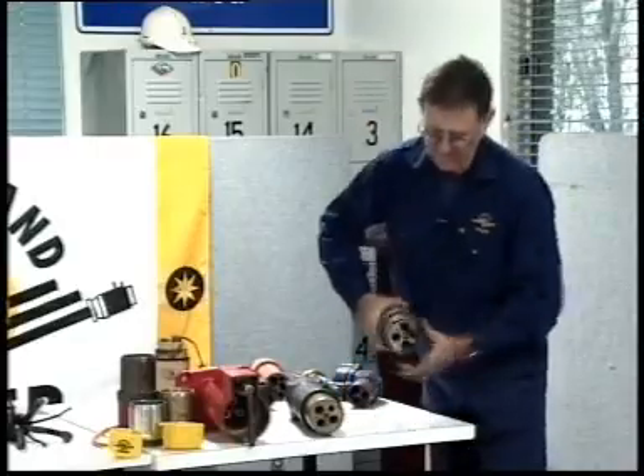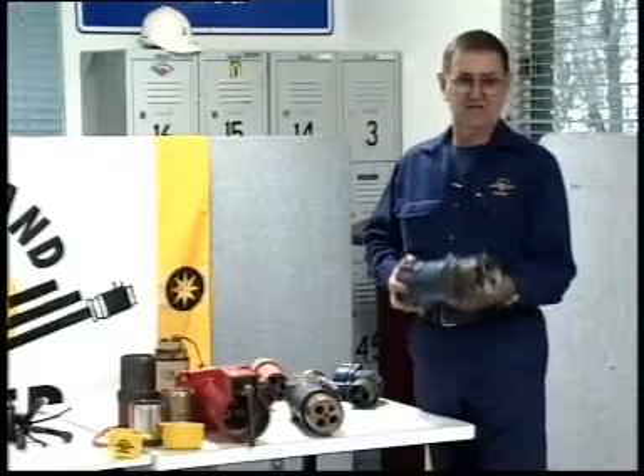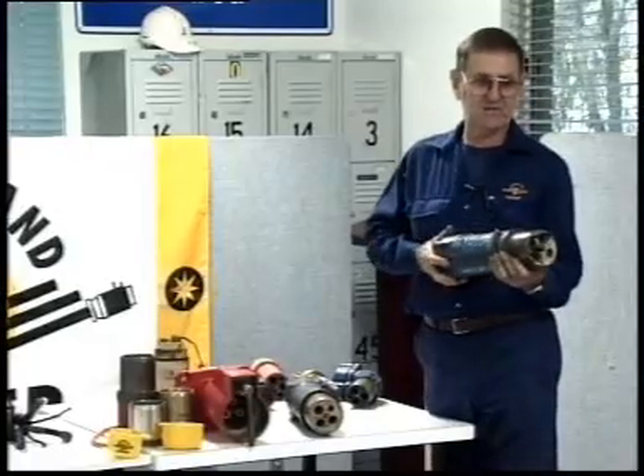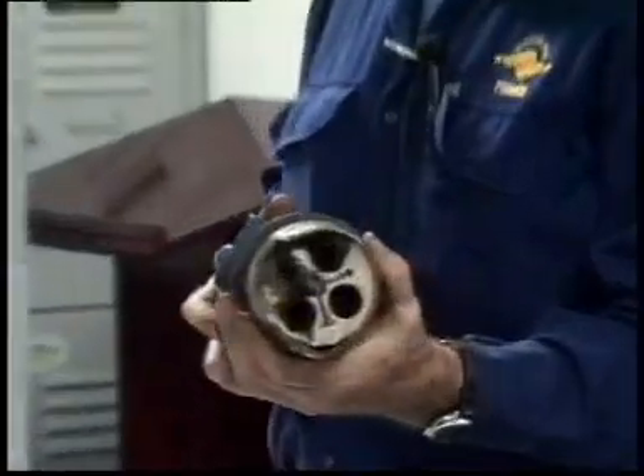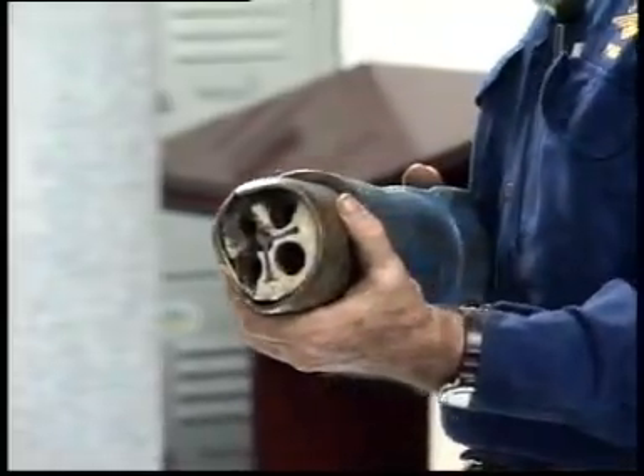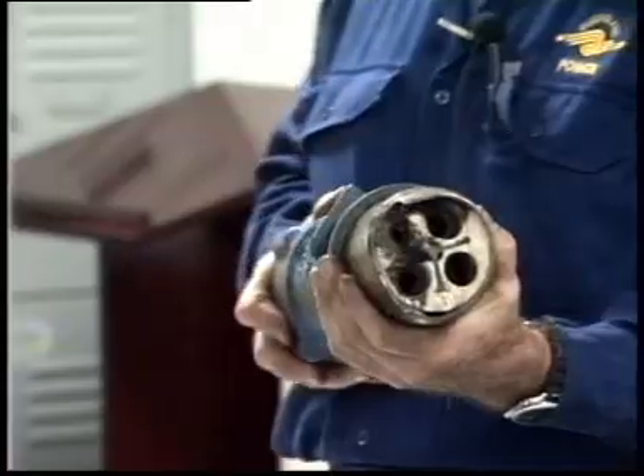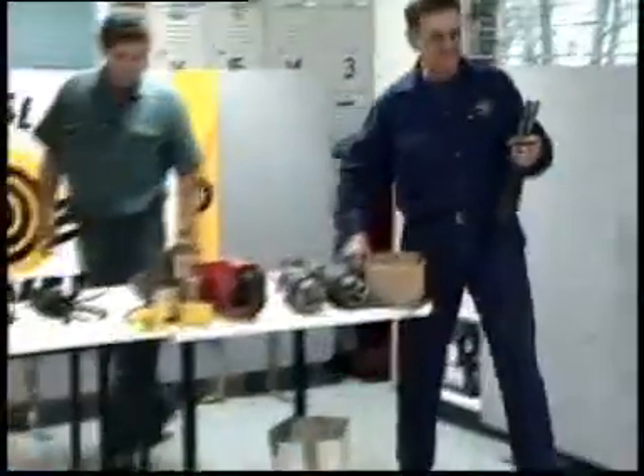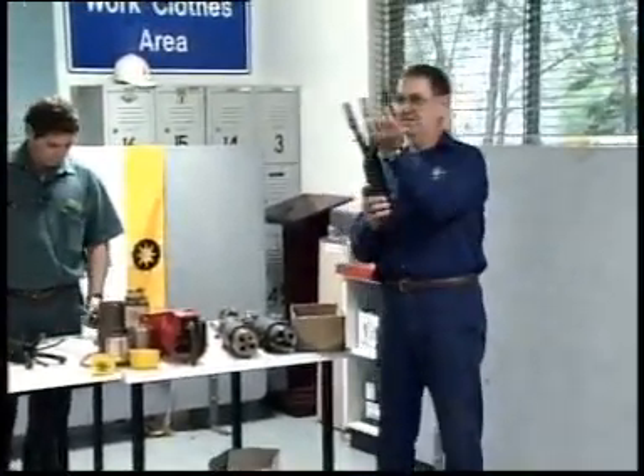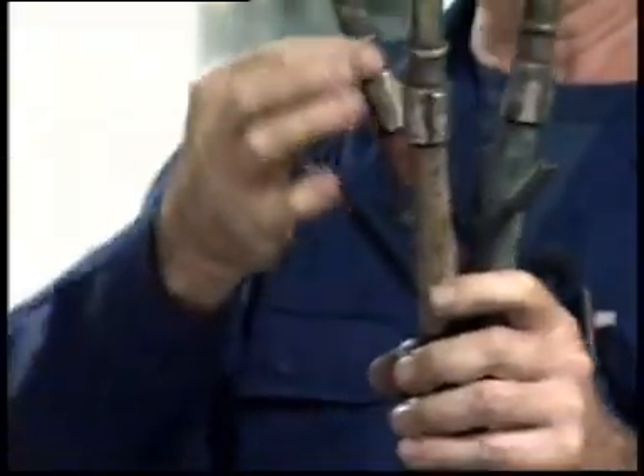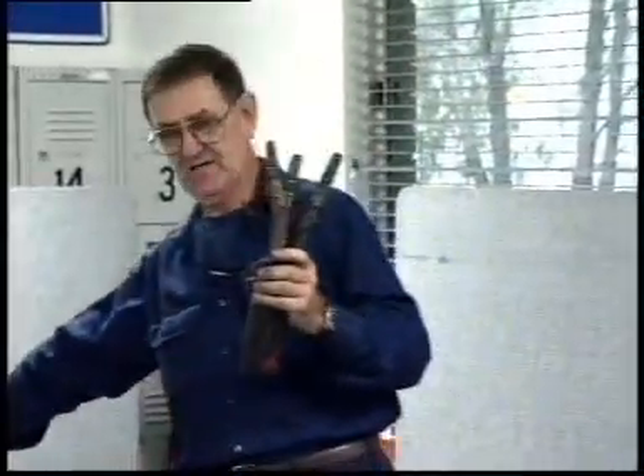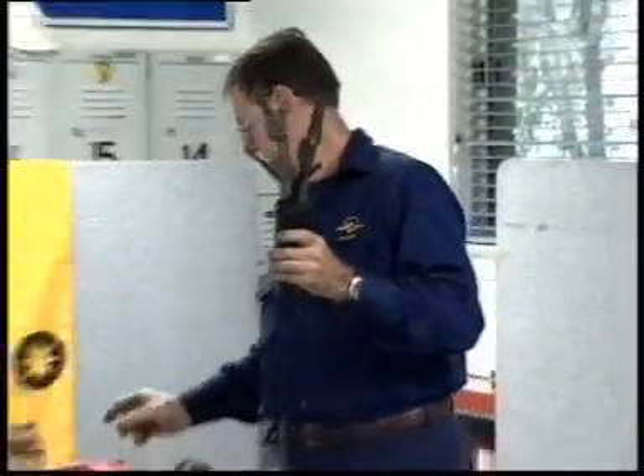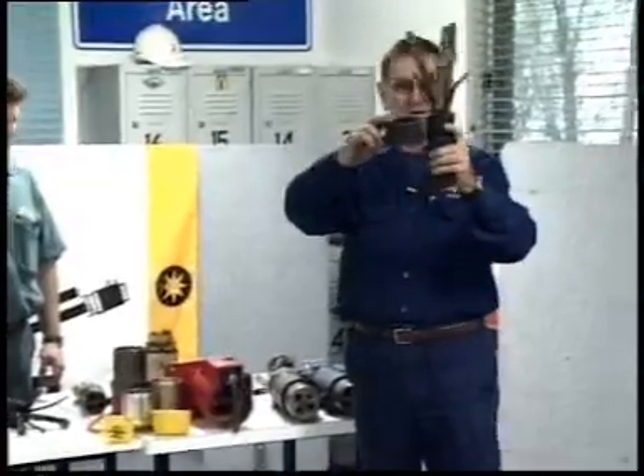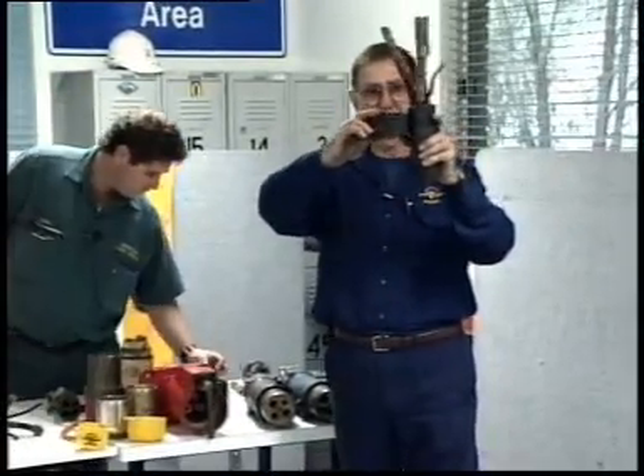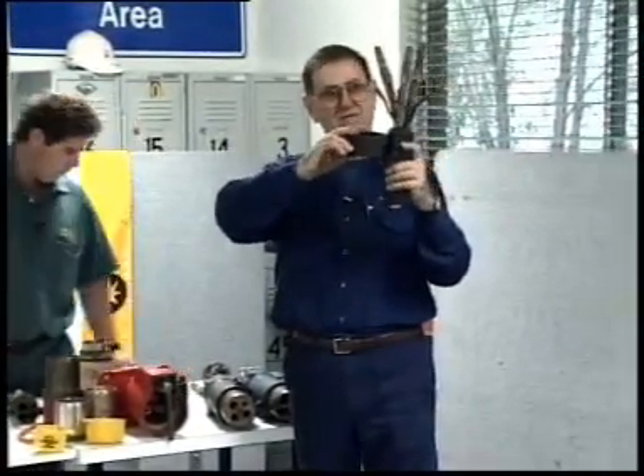This one here was pulled completely out of a machine. It's flashed. You can see all the burn marks inside it all the way through. And it's also broken the earth skirt on one side, completely snapped it off. This particular one here was in a situation at one of the mines. Remember I said before how the contacts and the thimbles at the back are locked in to that interior, and at the back we've got the neoprene cone that sits right there holding the cable mechanically strong into the plug, and the plug's filled normally.